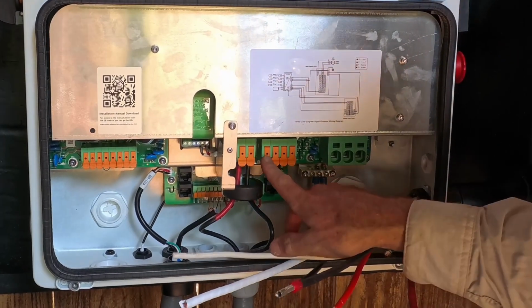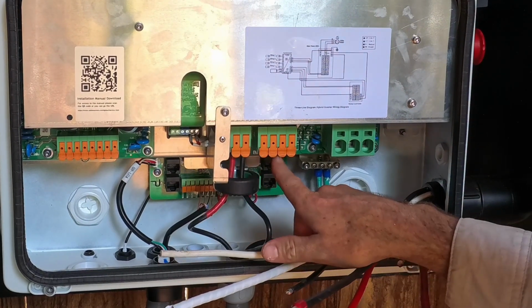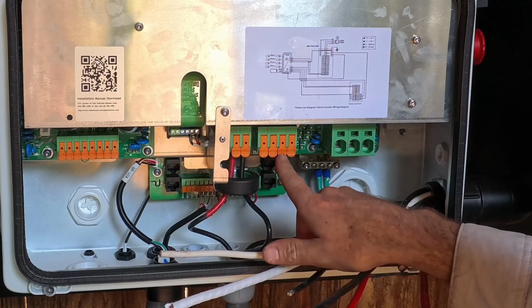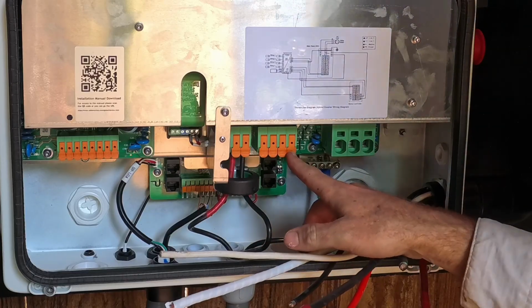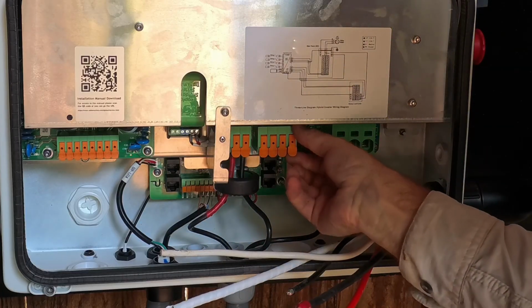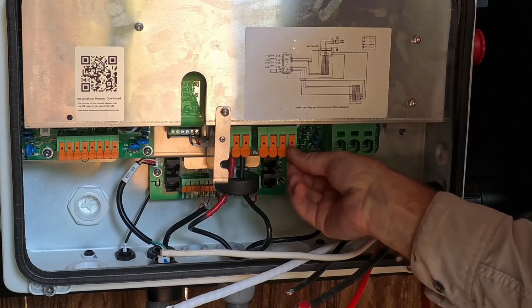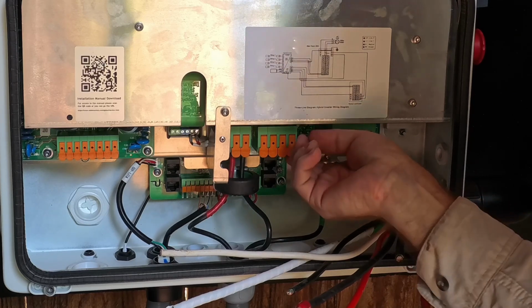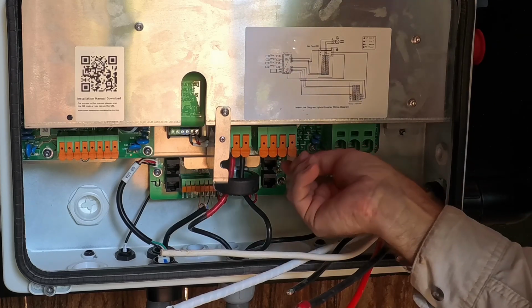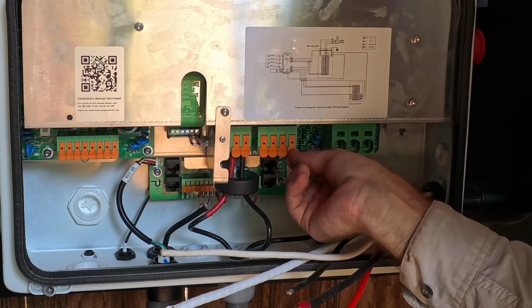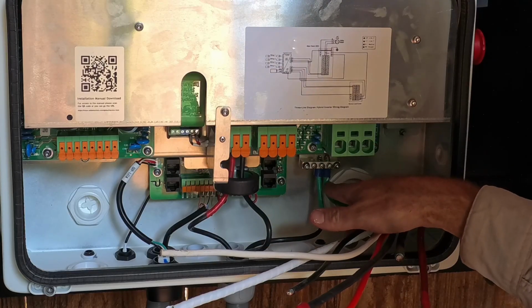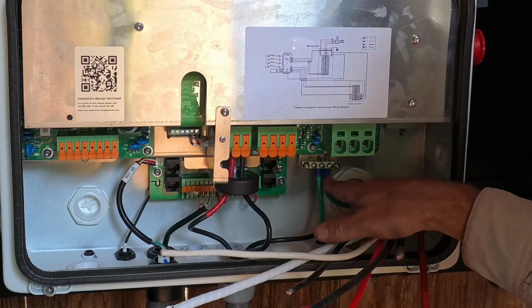So starting on the left, we've got L1, then L2, then neutral, and then ground. From what I've seen, this ground here is a dead lug, at least that's what Kelly over at Signature Solar said. So I'm not going to use that. I've connected down here to the PE, or ground bar.